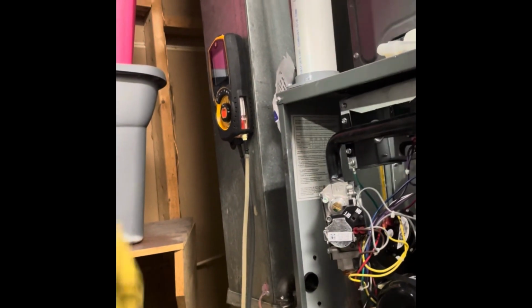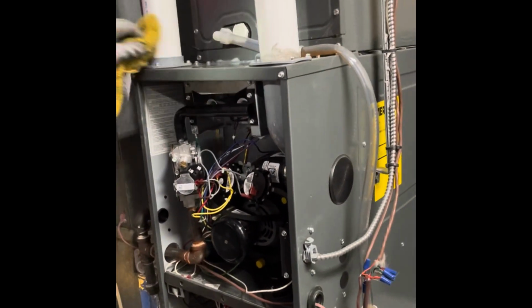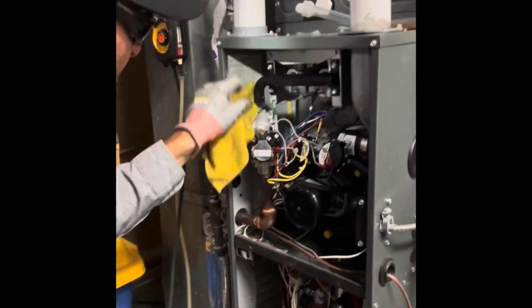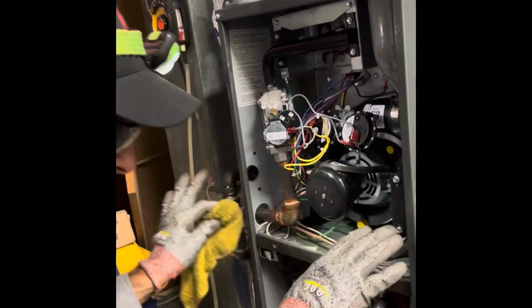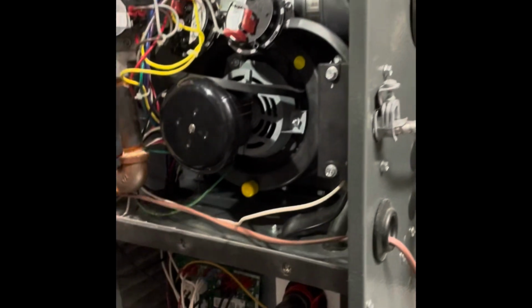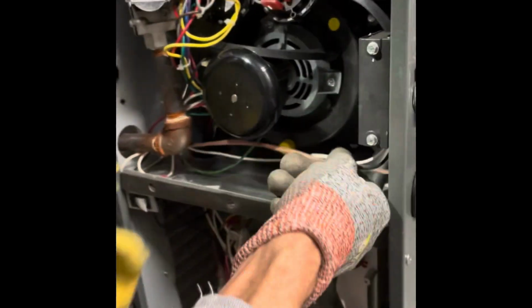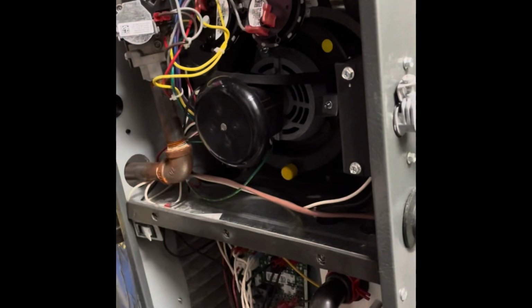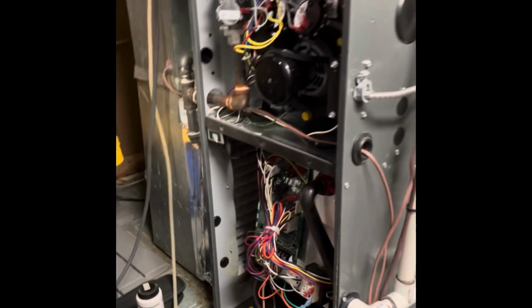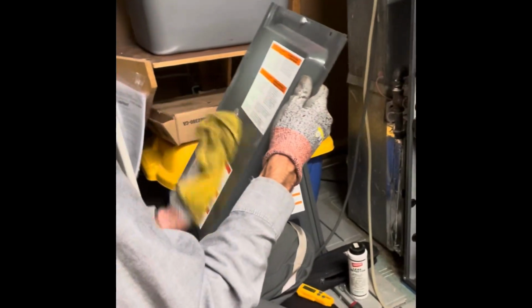So last but not least, on all my furnace maintenances, I always like to wipe down the furnace before I put the doors on, because we do get a lot of dust accumulating everywhere over time. So I'm going to wipe his manifold, just make sure the gas valve's good, checking down here for any leaks. Gaskets at the back leak a lot, so I want to make sure I'm not seeing any visible signs of that. As for the doors, I'll wipe them down and then I'll put his furnace door back on. And I've got to do a leak test at that port I've tapped into to check his gas pressure, just to make sure I don't leave him with a leak.